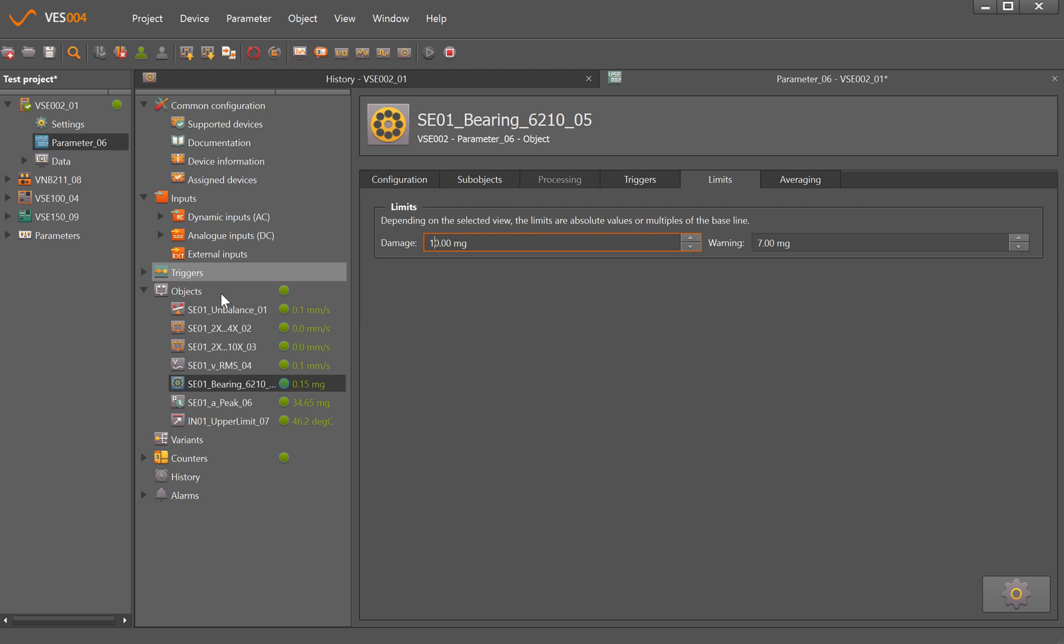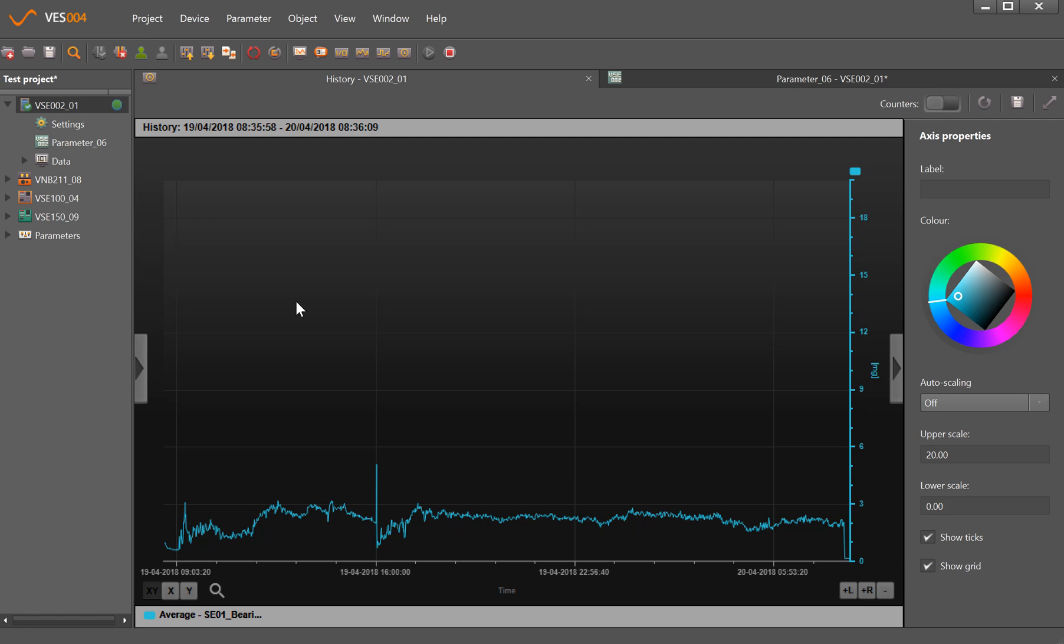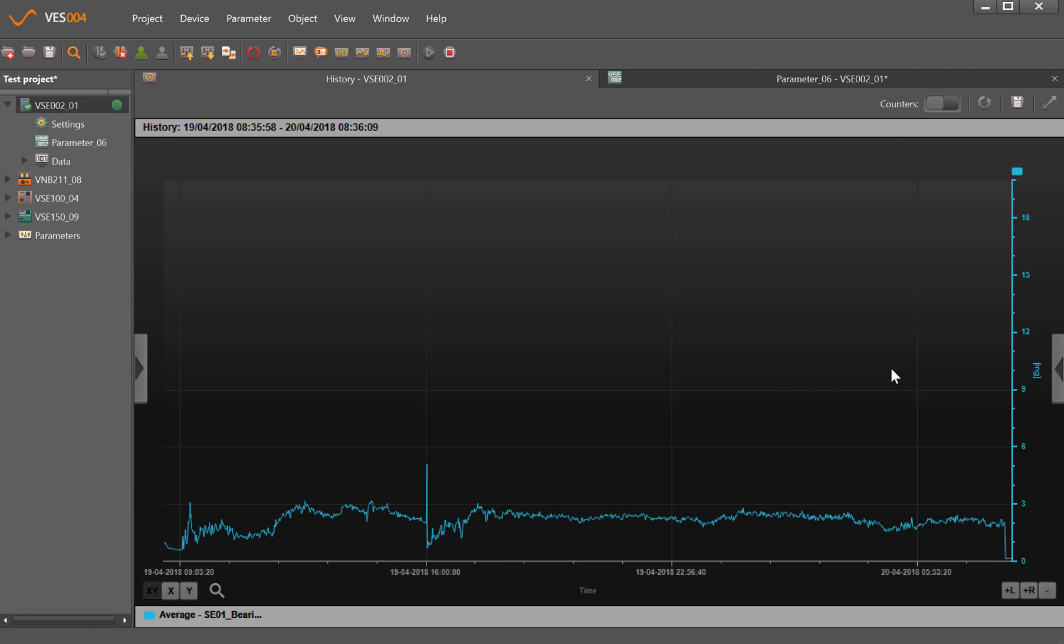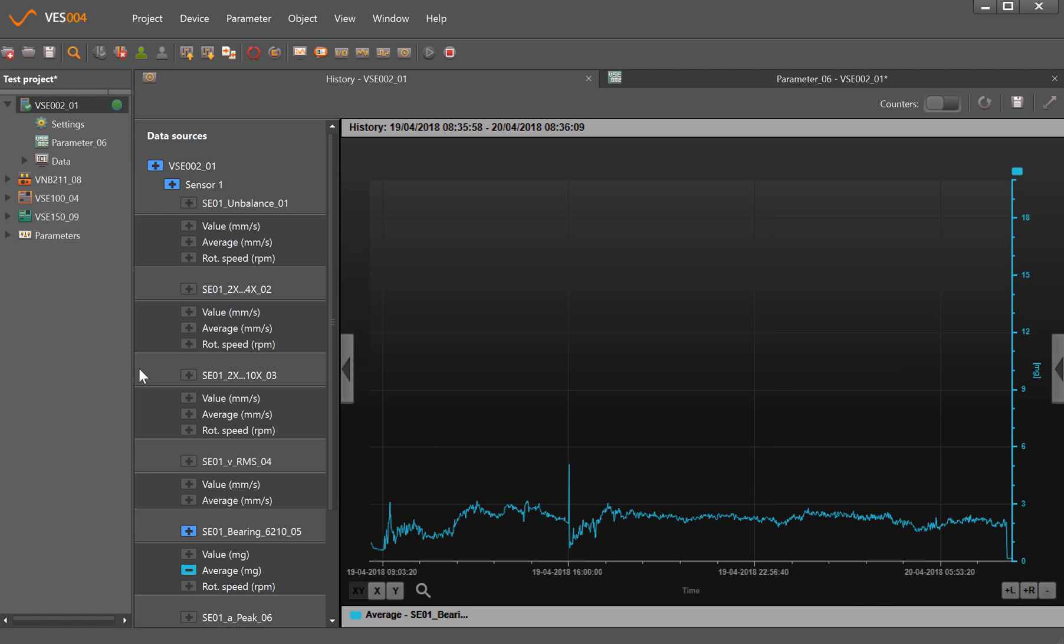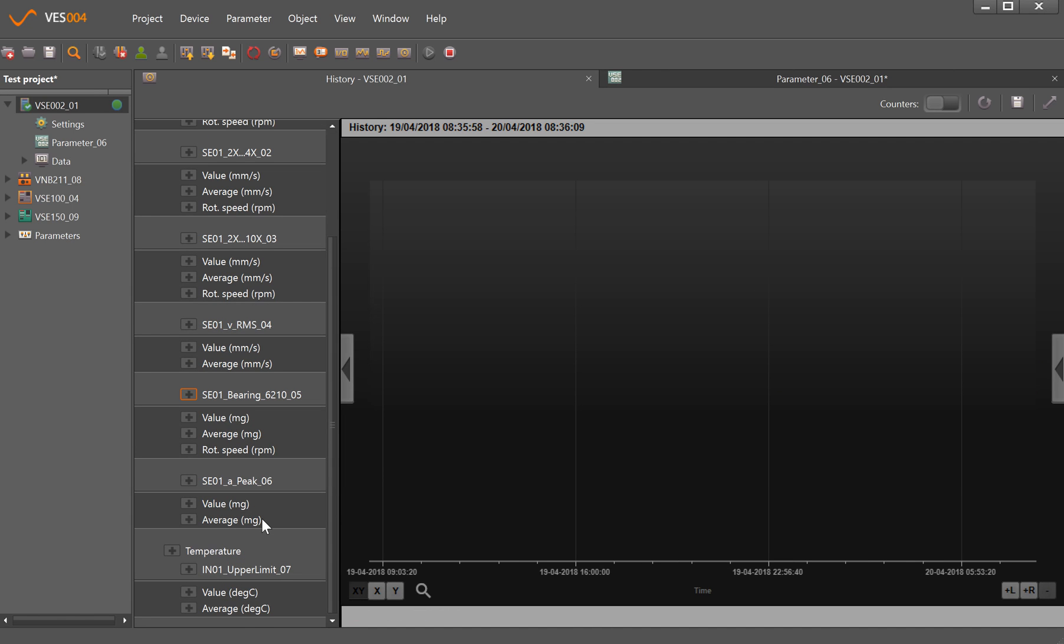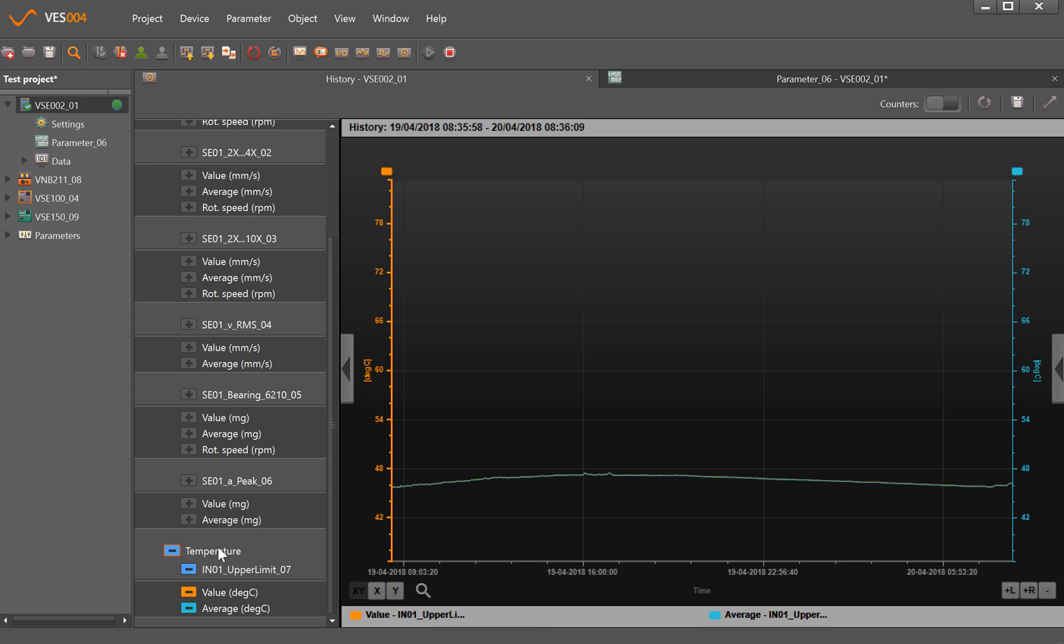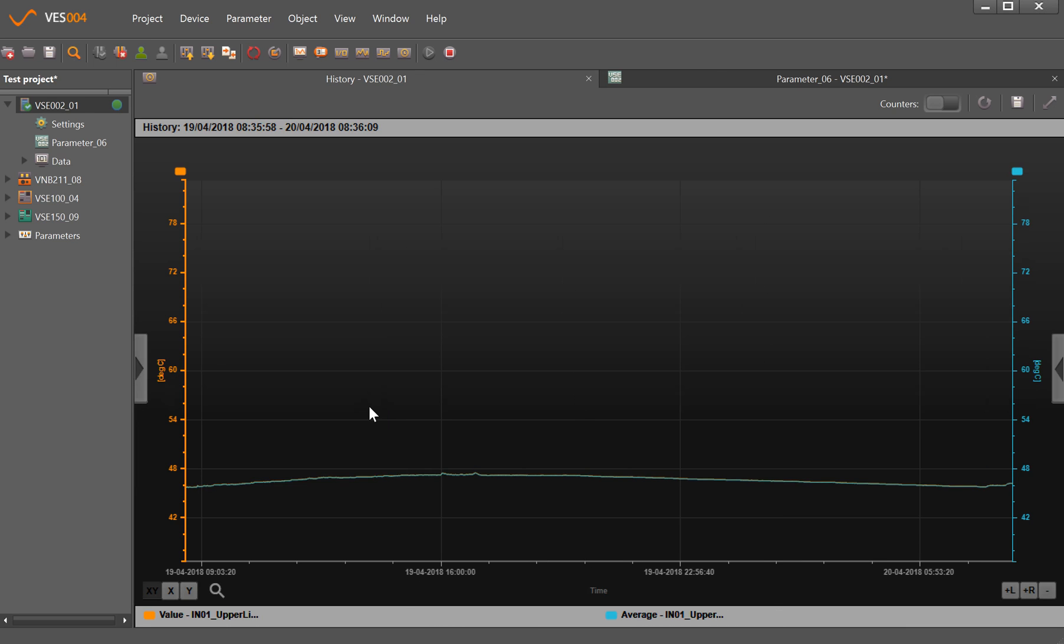Now before I'm going to upload that revised parameter set, I'll go back into the history and just check, say for example, the temperature. So if I just make that bigger there and come here, we'll just remove the bearing and we'll scroll down to look at the temperature. Okay, so that's given us the average and the maximum value. You can see we have the two axes here. If I click on one of these, it'll bring in where my yellow and red limits are, and you can see it did go up very slightly but stayed below the level throughout the whole history trend.